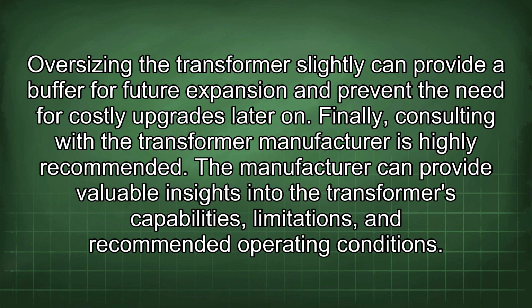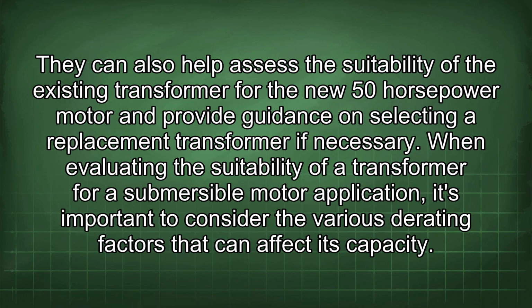Finally, consulting with the transformer manufacturer is highly recommended. The manufacturer can provide valuable insights into the transformer's capabilities, limitations, and recommended operating conditions. They can also help assess the suitability of the existing transformer for the new 50 horsepower motor and provide guidance on selecting a replacement transformer if necessary.